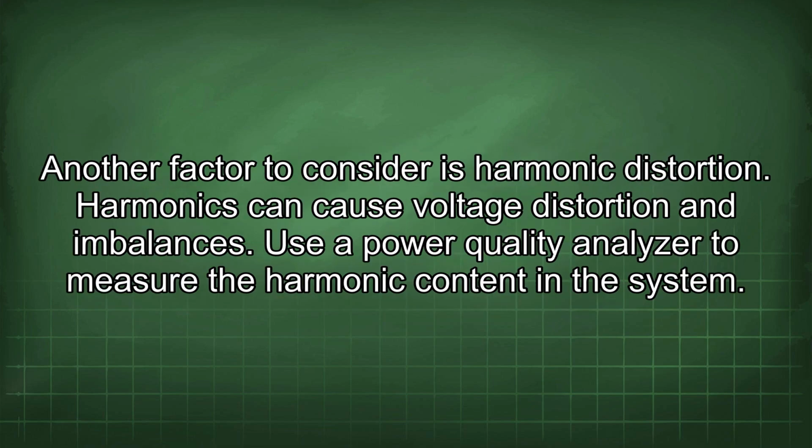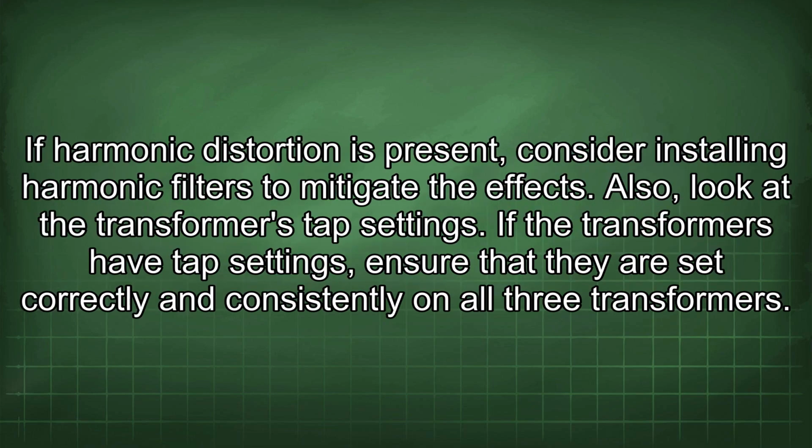Another factor to consider is harmonic distortion. Harmonics can cause voltage distortion and imbalances. Use a power quality analyzer to measure the harmonic content in the system. If harmonic distortion is present, consider installing harmonic filters to mitigate the effects.